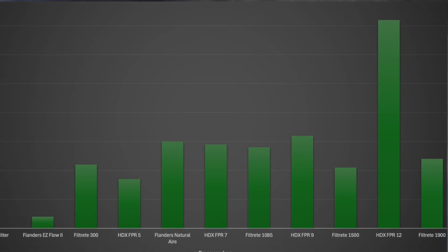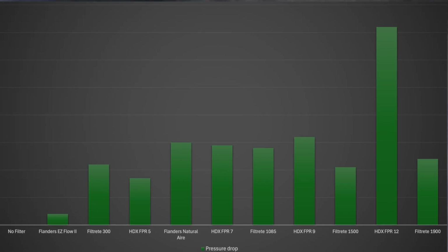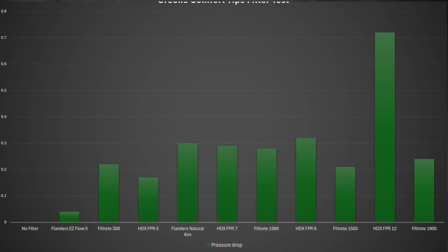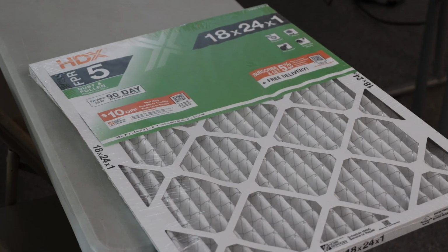Honestly, I think this test demonstrates something really important. The lesson here is not that everybody should immediately run out and buy the highest MERV filter they can find. The lesson is that airflow restriction is more complicated than the number printed on the box. Filter design matters, the pleat density matters, the surface area matters, construction quality matters, and if you're trying to balance good indoor air quality with good HVAC system performance, you need to look deeper than just the marketing claims or MERV rating alone.